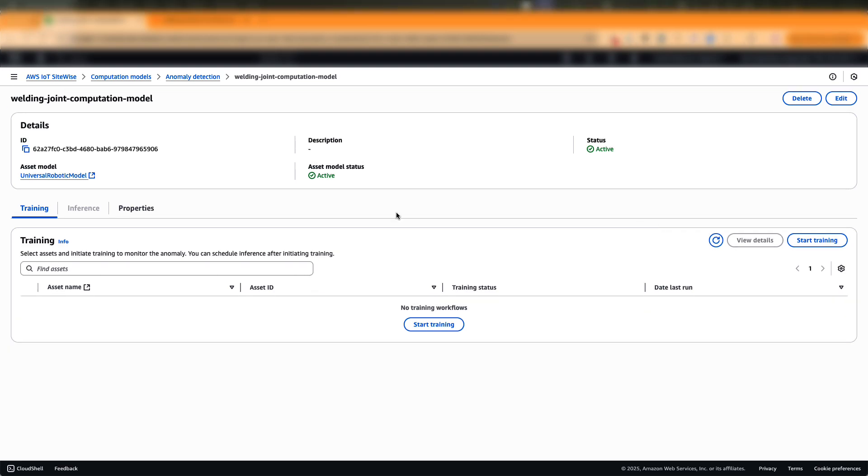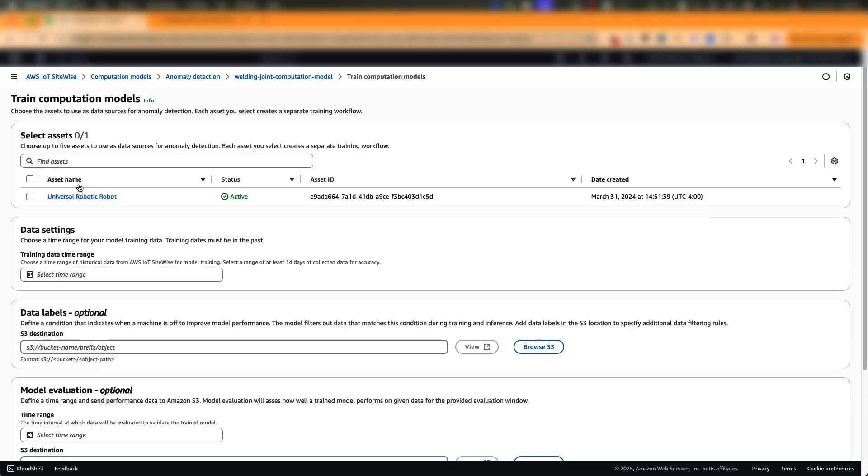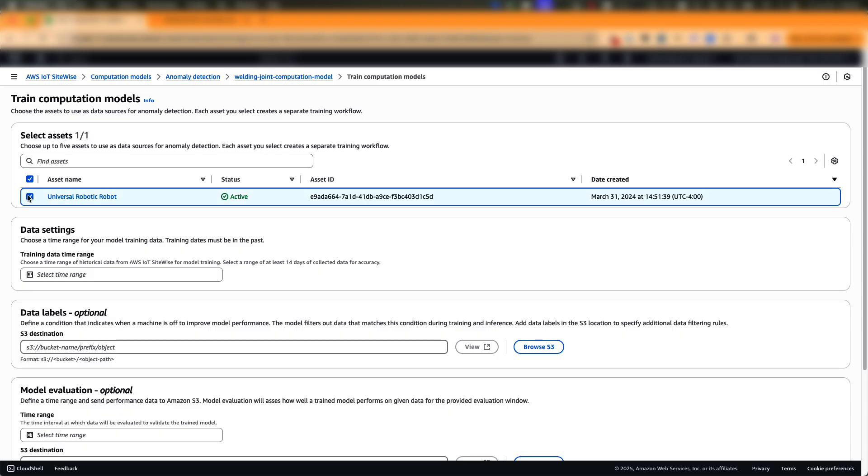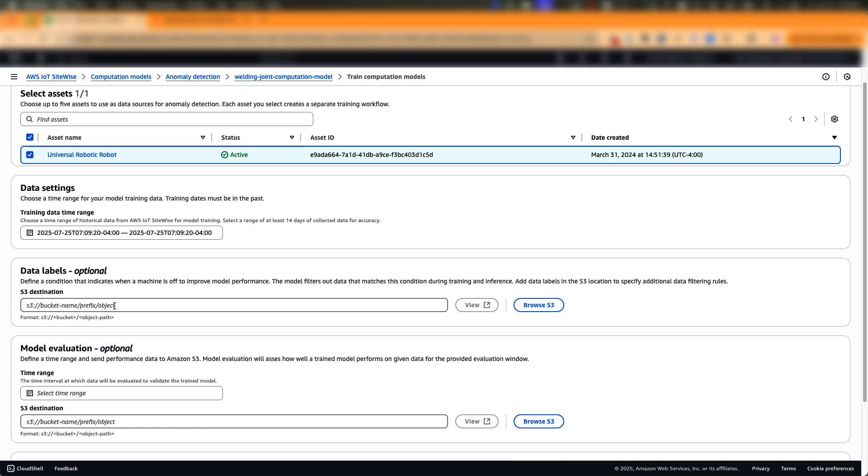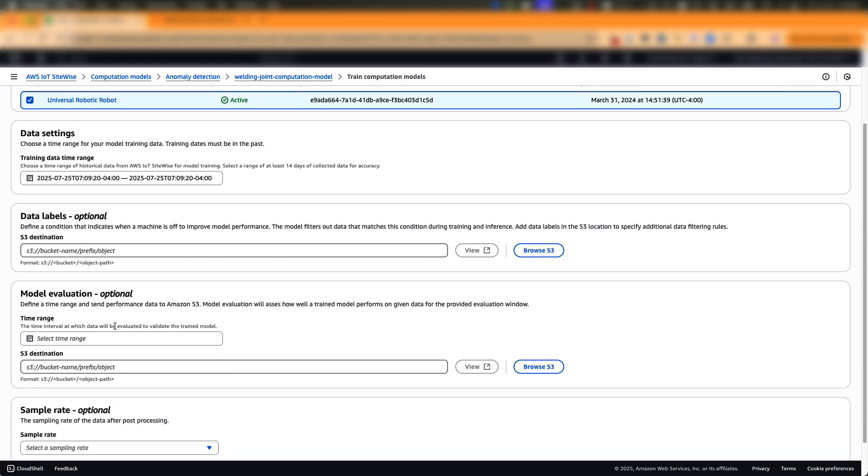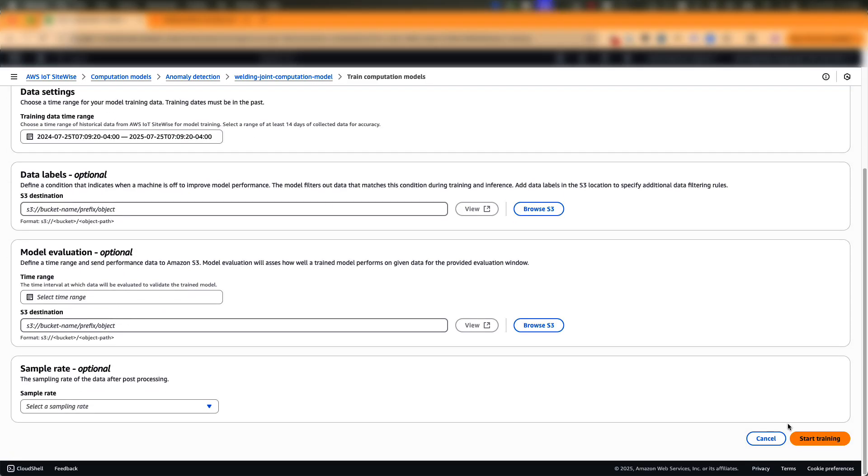To train the model, you have to choose your template first. Since we are already in our newly created template, we are good to go. Select start training and pick your asset. So in this case, we'll use the welding robot and choose your training data range. In this case, I'll pick one year and use any labels from your maintenance records to further improve the model training performance. Next, you could also choose an evaluation data range to assess the training performance. This really helps you decide if the model is good enough for you to promote it to production environment. And finally, start training.